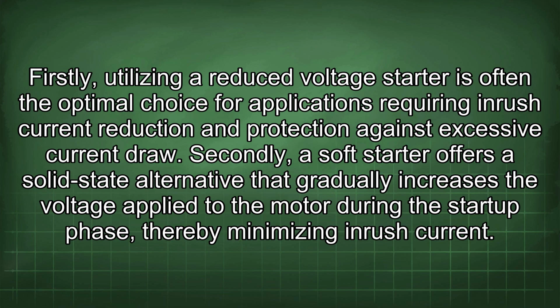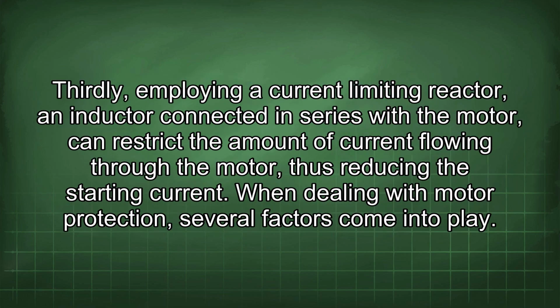Secondly, a soft starter offers a solid-state alternative that gradually increases the voltage applied to the motor during the startup phase, thereby minimizing inrush current. Thirdly, employing a current-limiting reactor, an inductor connected in series with the motor, can restrict the amount of current flowing through the motor, thus reducing the starting current.